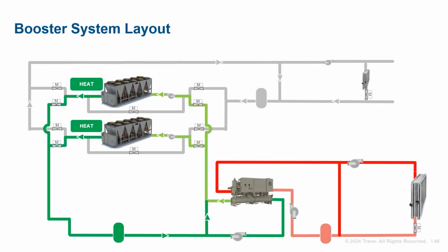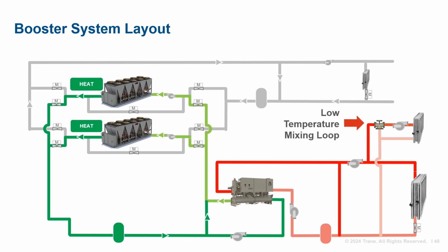But what if we have existing coils selected for higher temperatures and new coils selected at lower hot water supply temperatures? In cases where a new renovation or addition must be tied into the existing building hot water heating system, but it's designed for lower heating temperatures, a second piping loop with a mixing valve can be added to the system to achieve both hot water supply temperatures. Designing the additional loop and mixing valve, instead of having the air-to-water heat pump satisfy the lower heating hot water temperature, sacrifices some efficiency, but significantly reduces control complexity and may improve the air-to-water heat pump capacity, lowering system first costs. Now that we've covered how to achieve higher heating temperatures, I'll turn it back over to Ronnie.